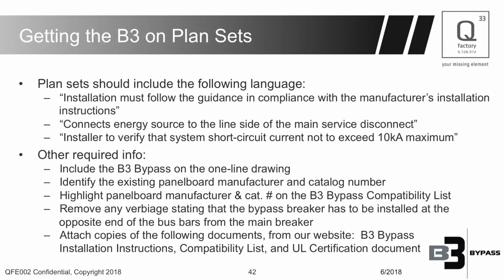This is common language for any manufacturer's equipment, but we say installation must follow the guidance in compliance with the manufacturer's installation instructions. So we recommend you put that on. Additionally, connects energy sources to the line side of the main service disconnect. Again, put this on the plan set so the plan checkers, when you submit it, realize that it's the line side, which means we now no longer are limited by the NEC 120% rule of 20% backfeed. Okay. Add installer to verify that system short circuit current not to exceed 10 kA.